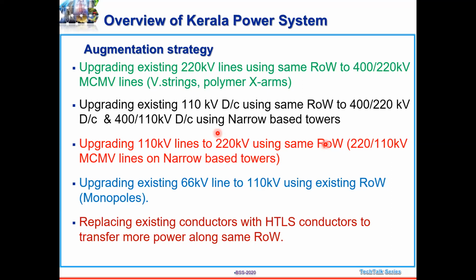That is also a first time in India, you can say. There is one used by PGCL for upgrading 110 kV DC to 400 kV single circuit, not a double circuit, but we are using it for a 400/110 kV DC multi-circuit line on the same right of way. And again, we are using 110 kV lines for upgrading to 220 kV using the same right of way, with narrow-based towers. 66 kV to 110 kV using the same right of way, using monopoles. That's also a new one in Kerala. We are using monopoles for that.